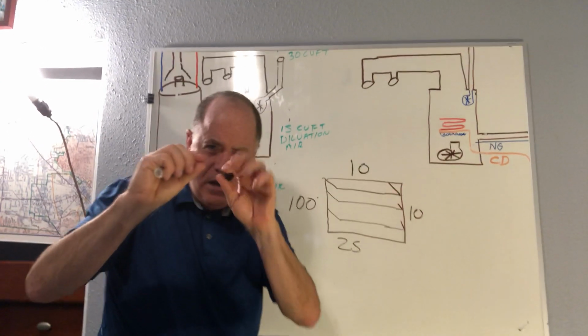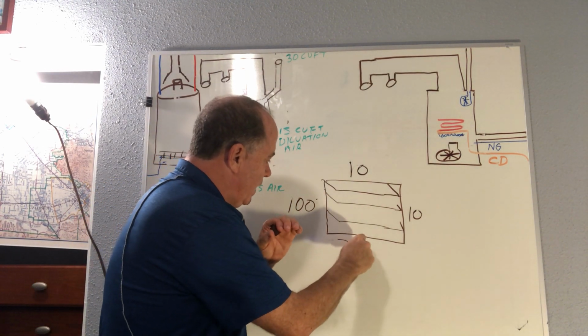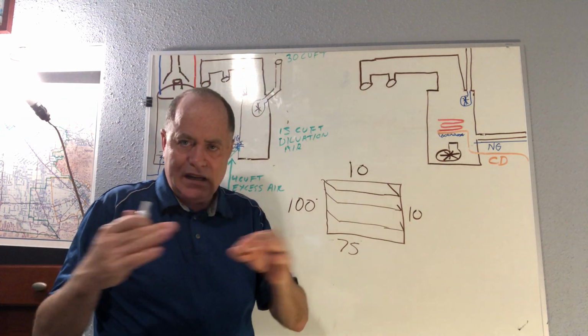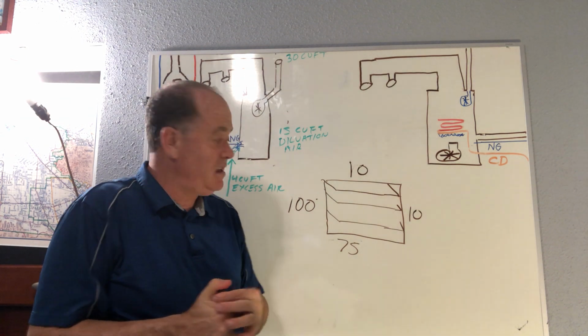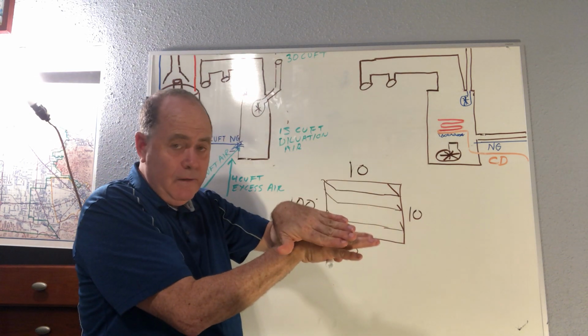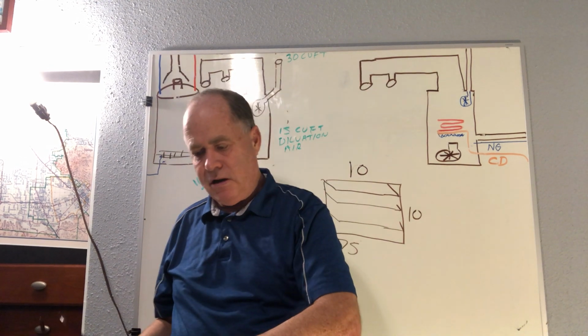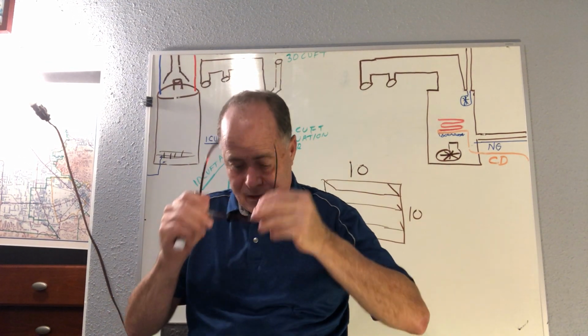However, if it's very thin metal louvers, then you could say, well, no, it's 75 square inches. So that's what they mean about the free area: you can't just say, well, I have an opening, because you have these louvers blocking a lot of that area. Okay, and I think that question shows up on a quiz that I give. All right.